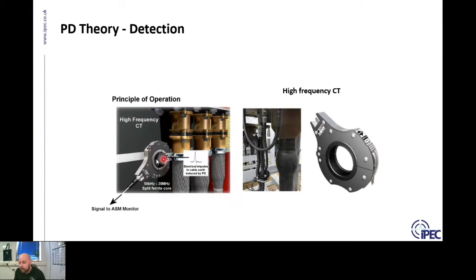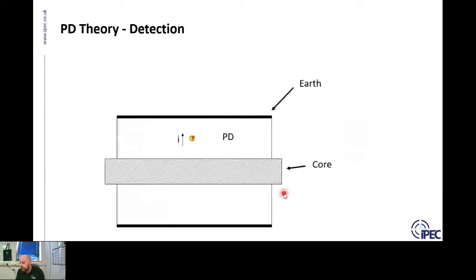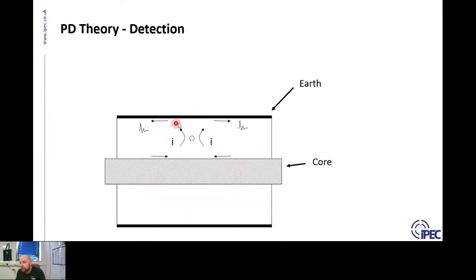HFCTs are quite commonly used for detecting PD in underground cables. If we take a cross section of a cable between two substations, when a small partial discharge occurs at a localized cavity defect — most likely in a joint — it induces a very high frequency signal on the inside of the earth sheath and on the outside of the core. PDs are very low in energy, and this high frequency signal doesn't carry much energy with it.